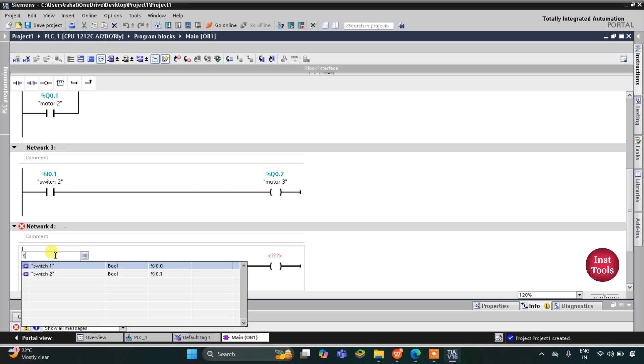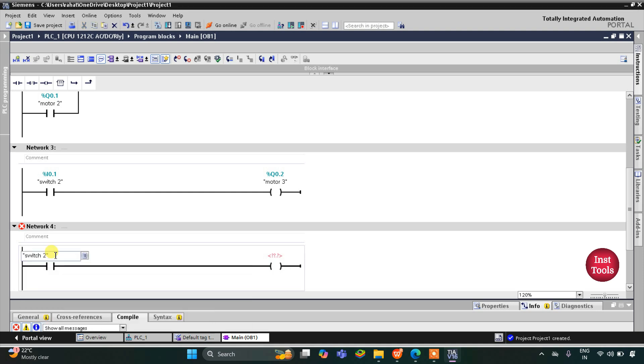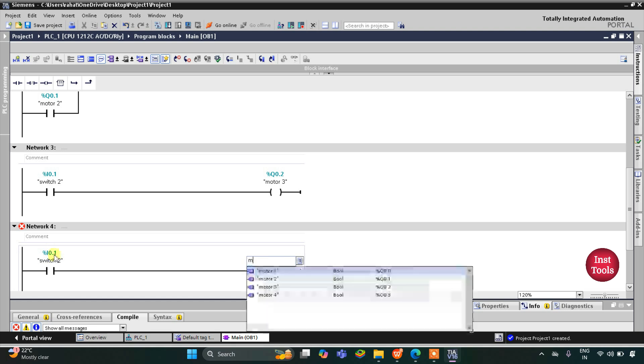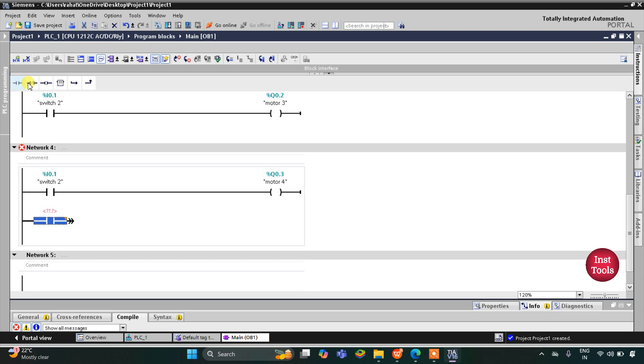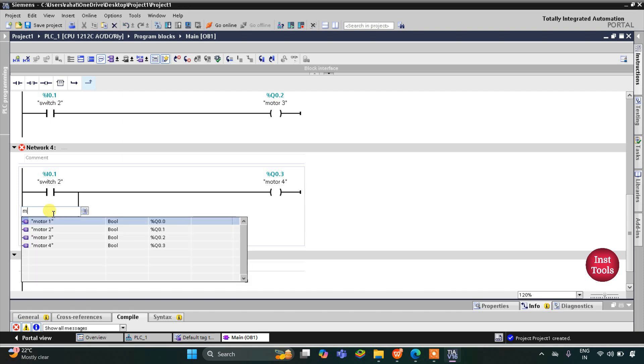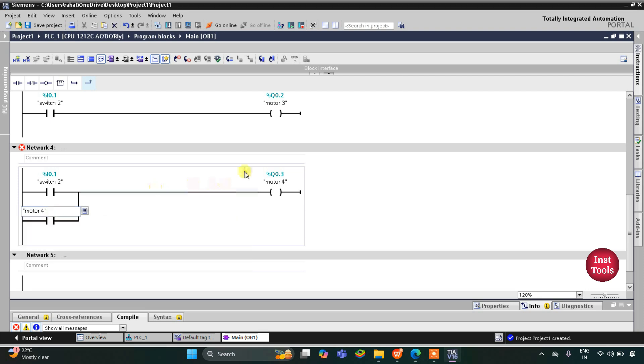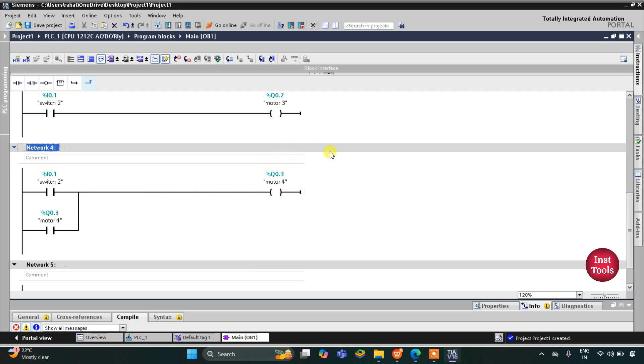I will use a normally open contact and a coil. This normally open contact will be switch 2 and this coil will be for motor 4. But when we turn off switch 2, motor 4 should remain on. For that I will open the branch here and add one more normally open contact — this will be motor 4. That is, we are implementing latching here, so motor 4 is now latched.